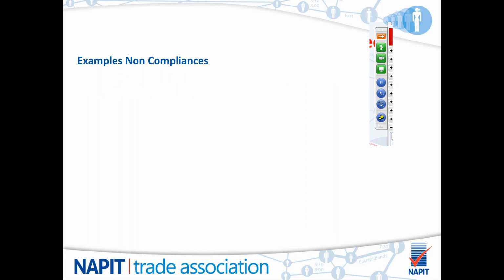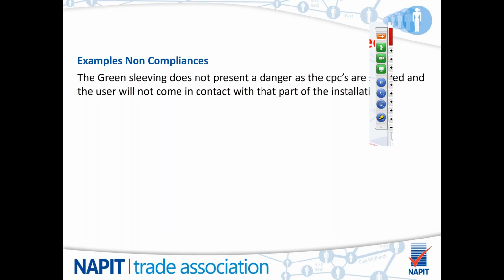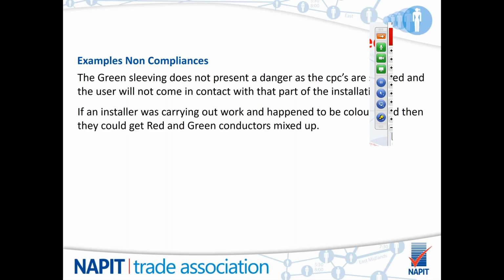It's just an example of non-compliance. It doesn't really rate a code. It doesn't present a danger in any way, shape or form. The CPCs are sleeved, the user won't come in contact with any part of that installation. If an installer was carrying out work and happened to be colourblind, admittedly they could get red and green conductors mixed up, but no code applies in this instance.